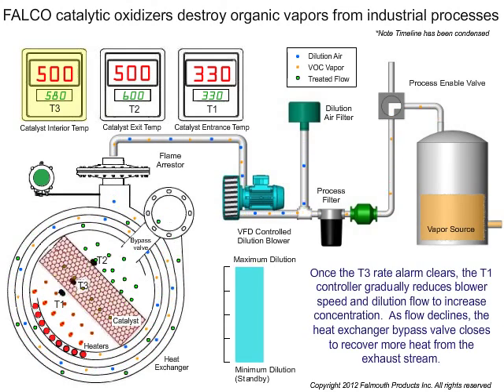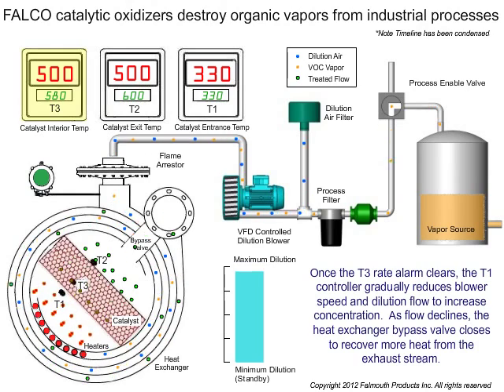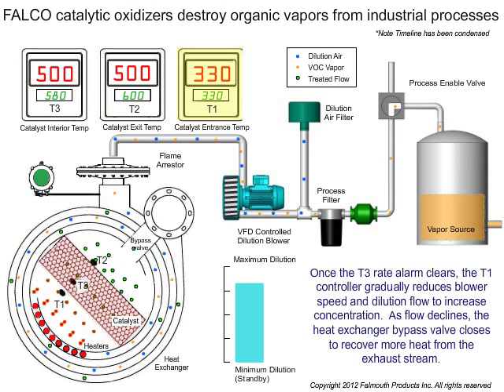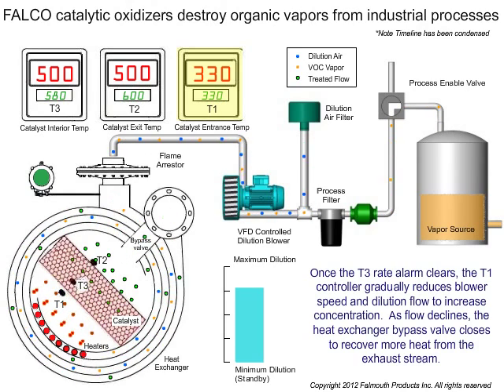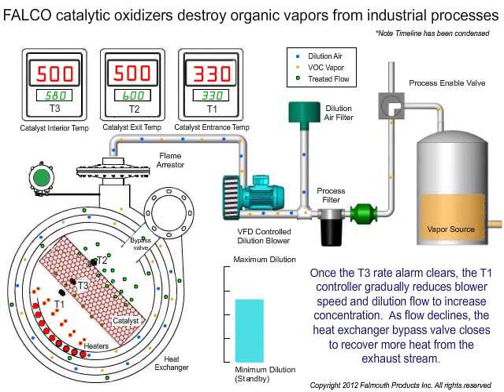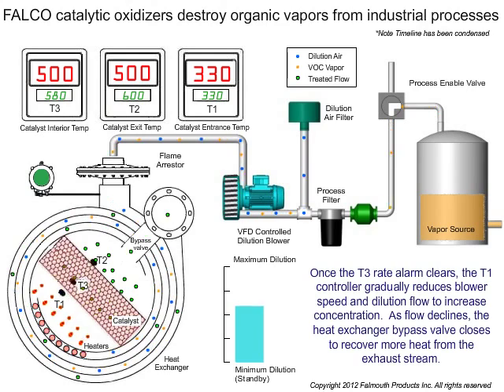Once the T3 rate alarm clears, the T1 controller gradually reduces blower speed and dilution flow to increase concentrations. As flow declines, the heat exchanger bypass valve closes to recover more heat from the exhaust stream.